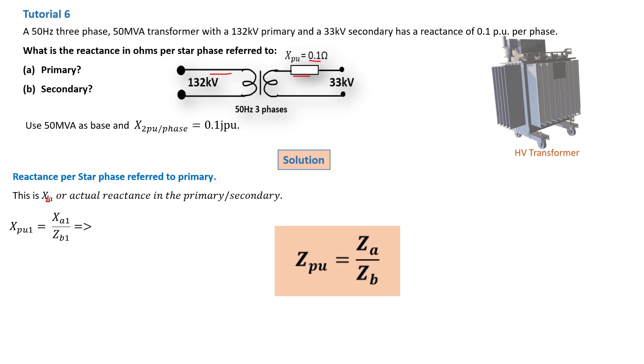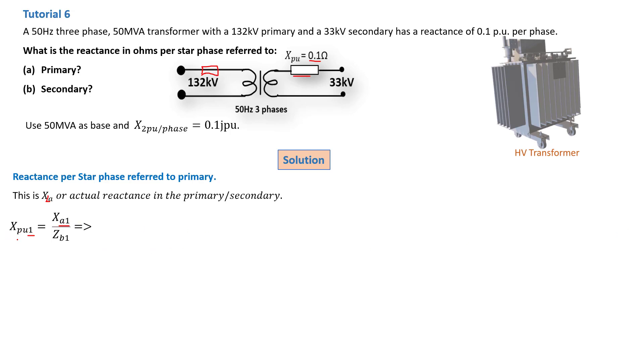The general formula is: X per unit 1 equals XA1 over ZB1, where subscript 1 denotes the primary and subscript 2 the secondary. XA1 would be the actual reactance on the primary of the transformer, but we don't have that value. We have X per unit 2 (secondary) but not X per unit 1, so we cannot directly find XA1. We must work the other way around — from the secondary back to the primary.